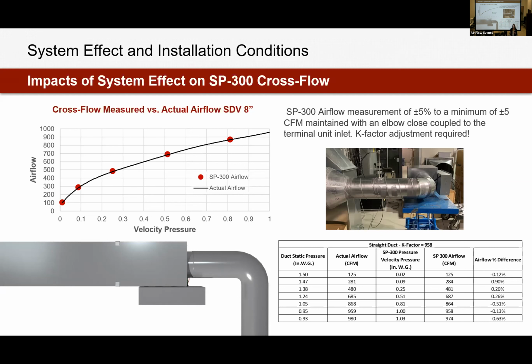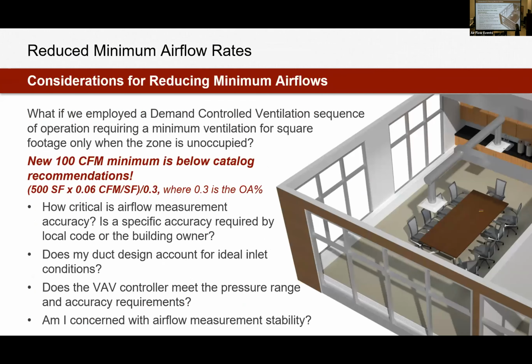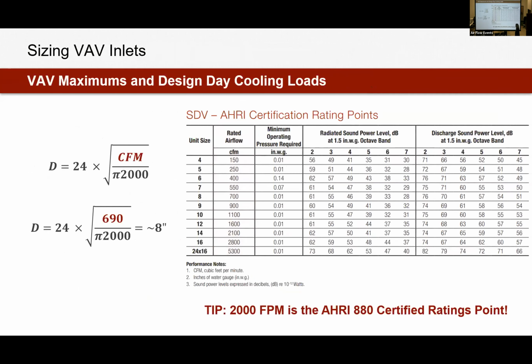So at test and balance on the controller, we had to set a constant in there to compensate for it. But as long as we were tested and balanced correctly from the beginning, we were able to maintain that airflow accuracy. Now, why is this possible? I wish I had another image of my crossflow sensor. It'd be annoying real quick.